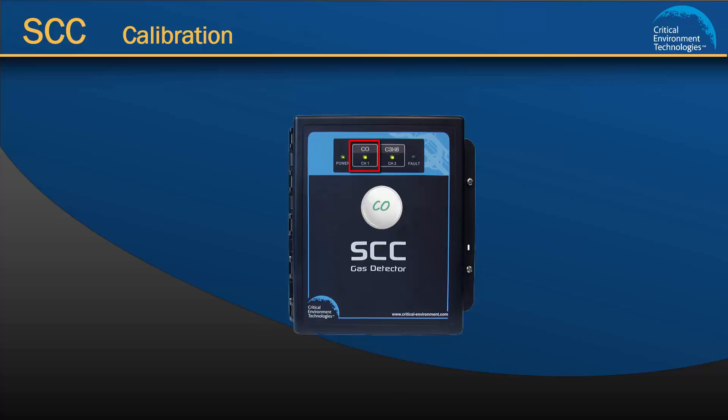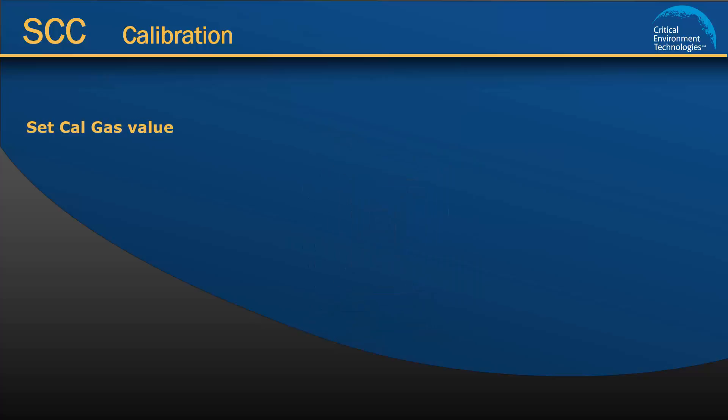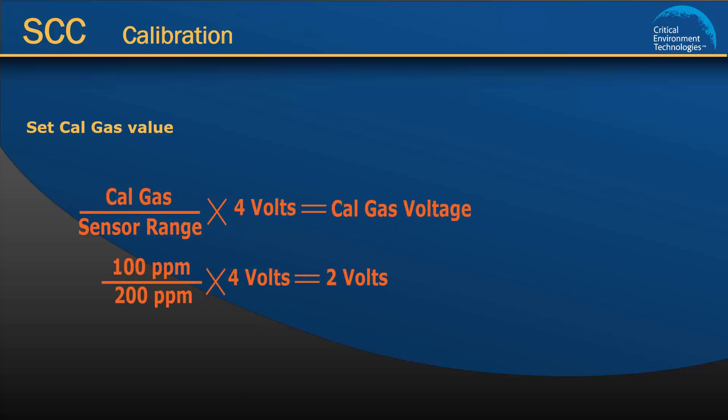There are three steps to follow when calibrating the SCC. The first step is to set the cal gas value. To calculate the value that needs to be set, you must use the formula shown on the screen. The values we know are: the factory set cal gas default for CO is 100 ppm, and the CO sensor range is 200 ppm. Using the formula, we are able to calculate that the cal gas value for CO is 2 volts.